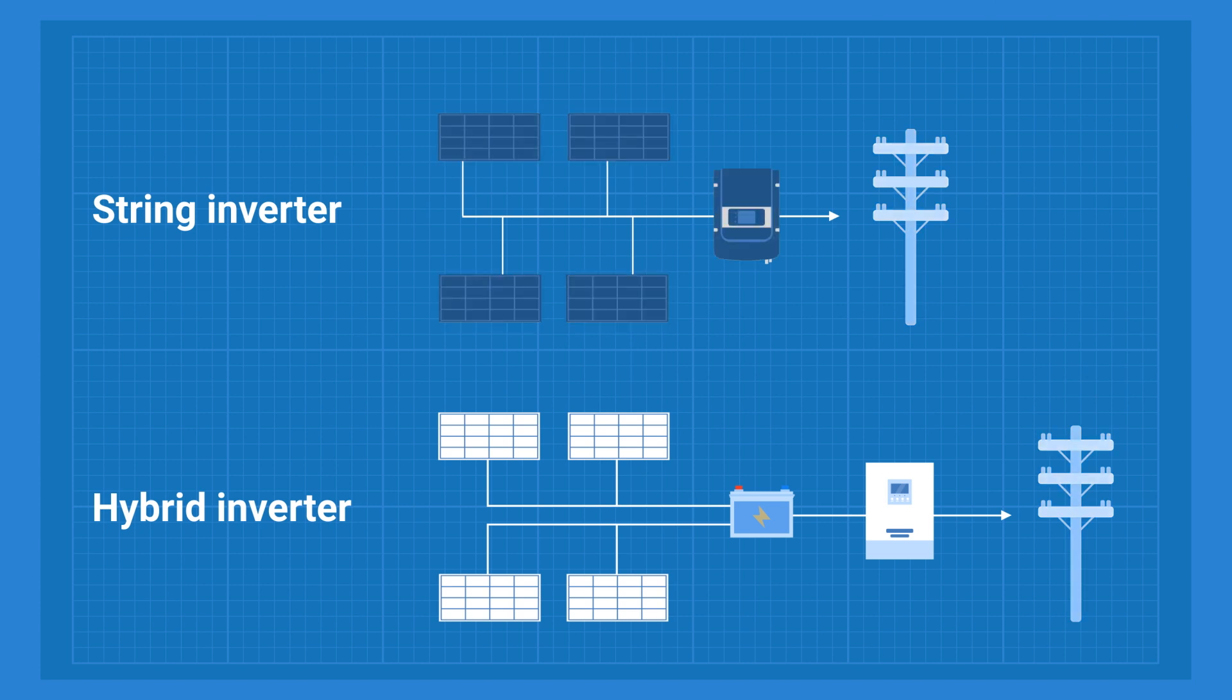When there is a power outage, a standard string inverter just shuts down - it's a safety requirement. The grid must be free of current for workers to repair it. This also means that you can't use energy from your solar panels during an outage. A hybrid inverter keeps the solar system running and switches your house to battery support.